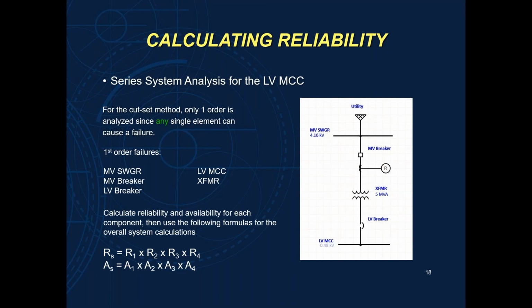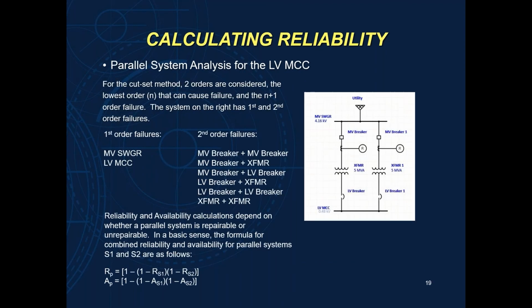Whenever you multiply percentages together, we all know that percentage will start to decline significantly. Okay, and we're going to do an example calculation here in a second. By comparison, in our other system, the parallel system, we have two first order failures, which would be the medium voltage switchgear or the low voltage MCC.